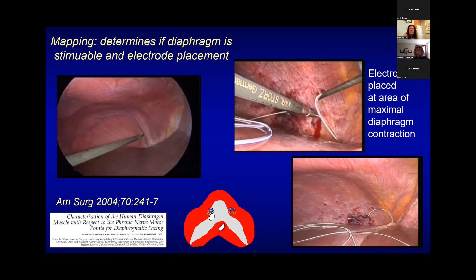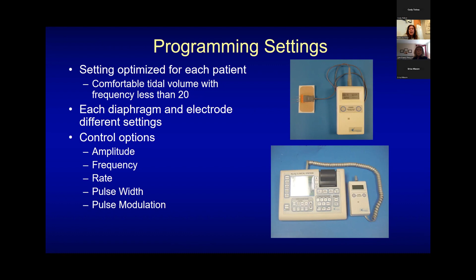So once we implant these wires, this is what the box looks like, and we can control and power each individual electrode. We get 2 electrodes to the right diaphragm, 2 to the left. And like I say, while they all go off at the same time, the actual individual power to the electrodes can be individualized. If somebody has maybe an incomplete injury, more sensation on the right or left, it can be tailored to their needs so that we can make it comfortable and still give them a big diaphragm contraction. So I had said earlier that this all started years ago.